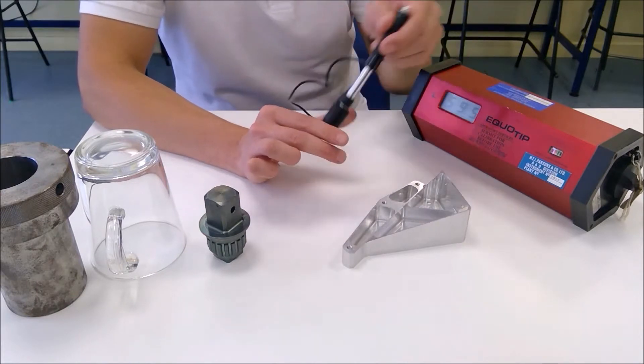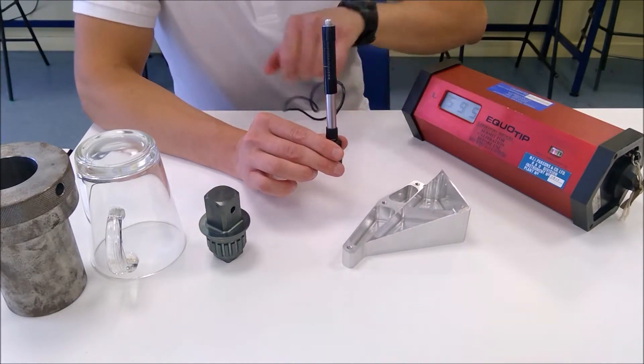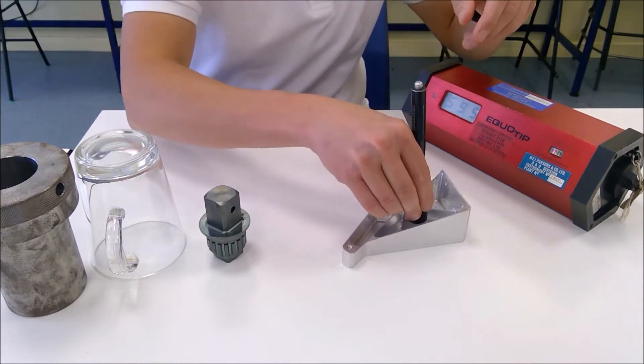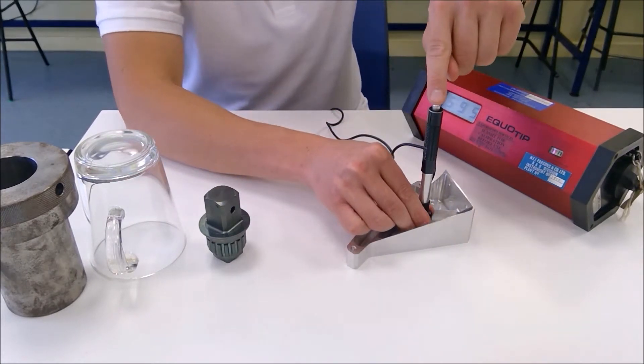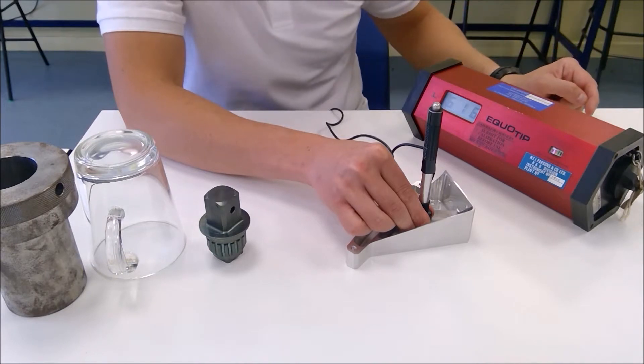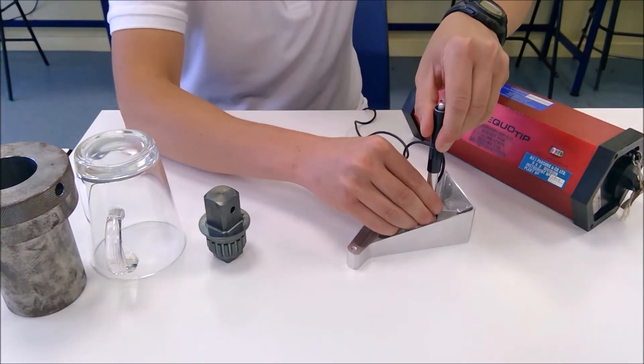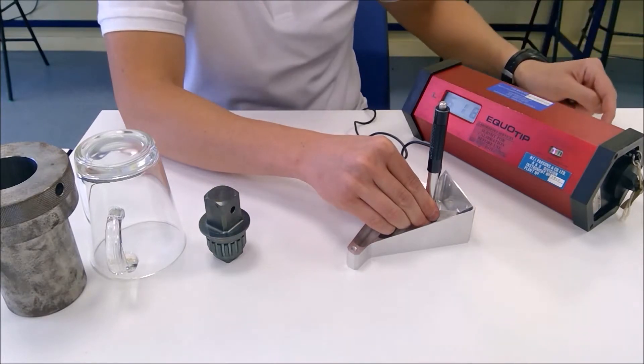So first of all let's begin with our aluminium and we already have our first reading for the aluminium of 595. So we're going to take a second reading, placing the probe against the surface and releasing the ball bearing. We have 616 and finally our third reading, again we have 618.